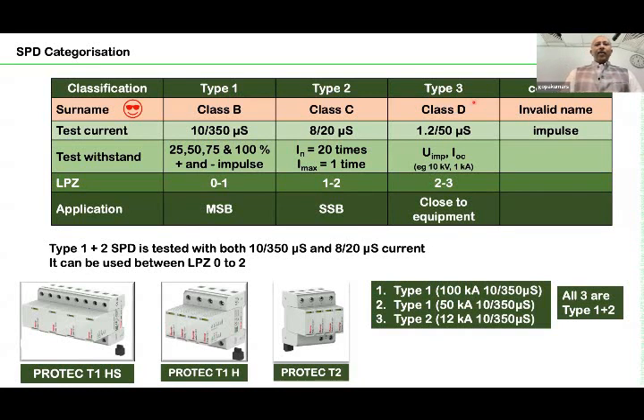Say, for example, this particular SPD which I have just shown you, the first one, the big one, is basically a type 1 SPD, 100 kiloampere, 10/350 microseconds. But in the specification it is written as type 1 plus 2, because type 2 parameters are also tested there. There is another type 1 SPD, 50 kiloampere, the third picture, with type 2 at 12 kiloampere, 10/350, and all these SPDs can be called type 1 plus 2. But I show this table on the right side because type 1 plus 2 is not a meaningful term, whereas these current ratings of 100K, 50K and 12K are meaningful. So you should look at the current ratings.